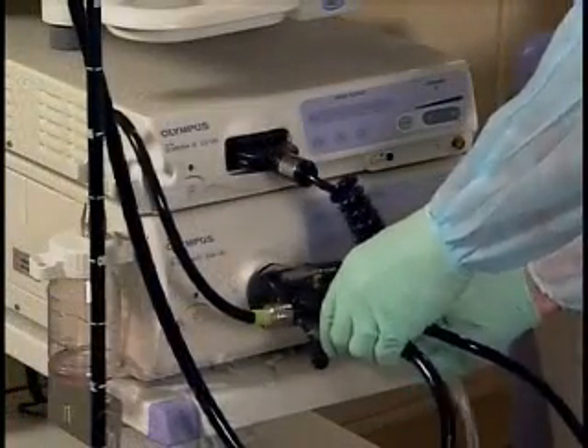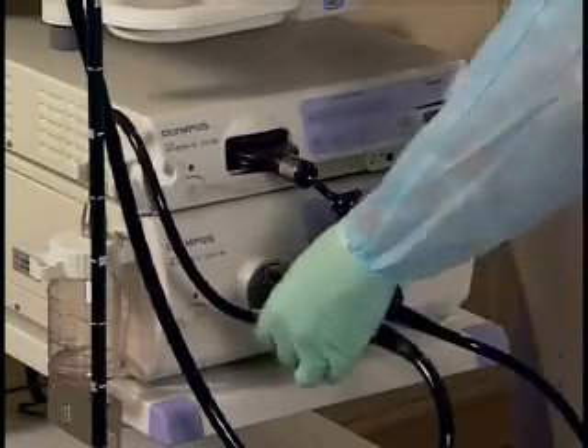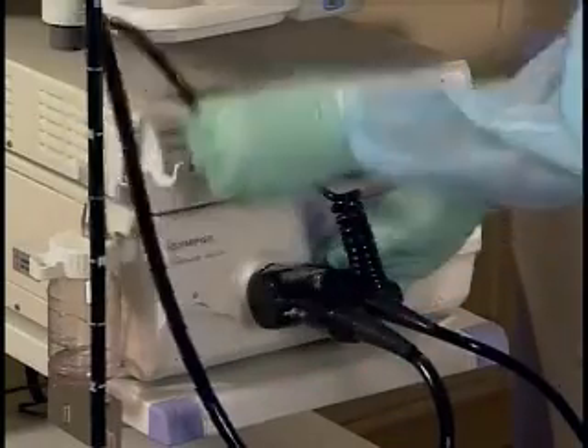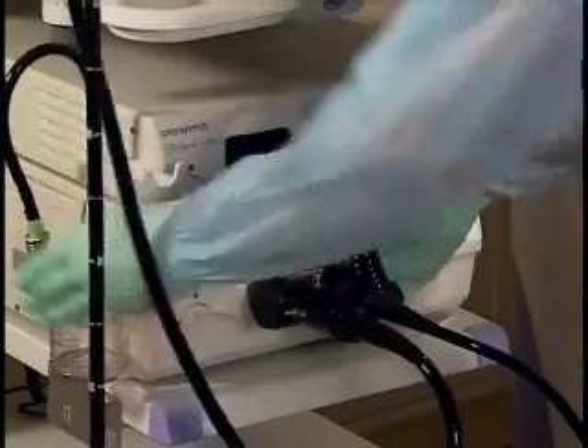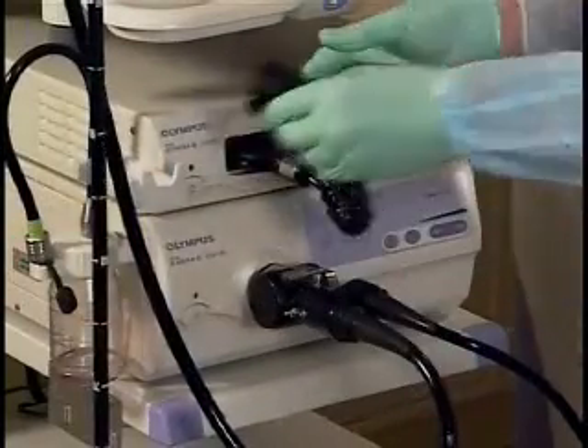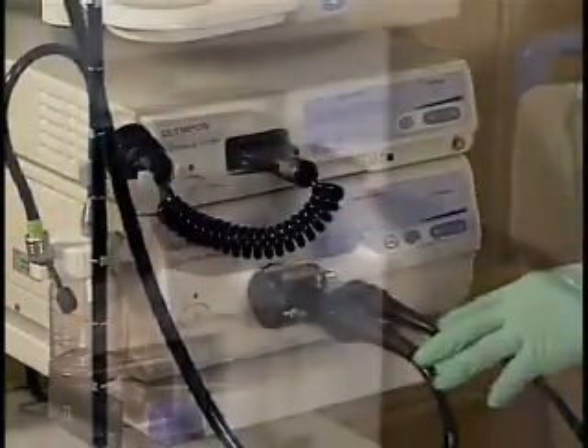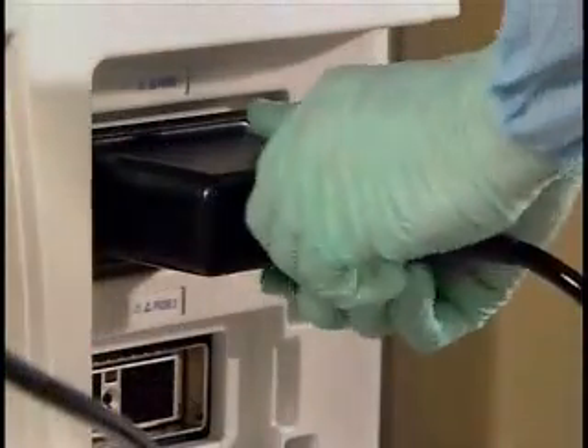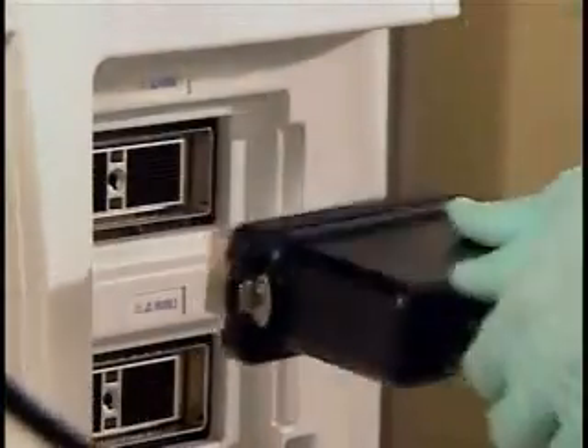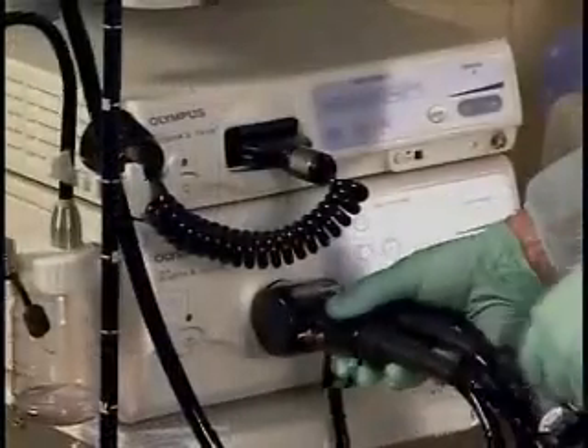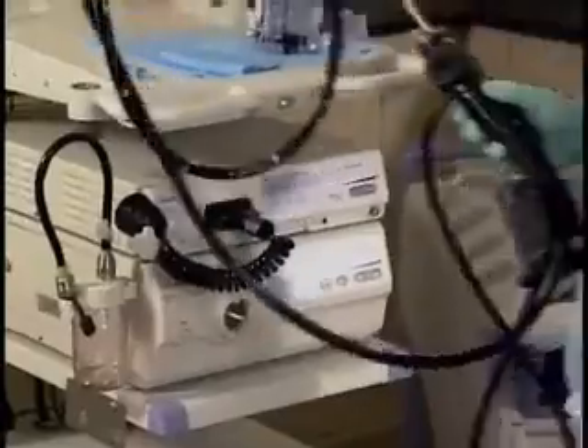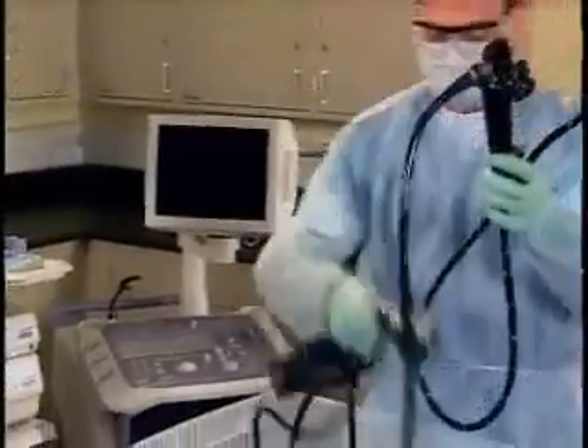Disconnect the suction tube, water container, and videoscope connector. Disconnect the ultrasound connector from the ultrasound system. Disconnect the endoscope from the light source. Now, carefully transport the endoscope and accessories to the reprocessing room.